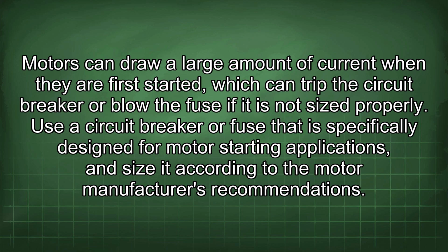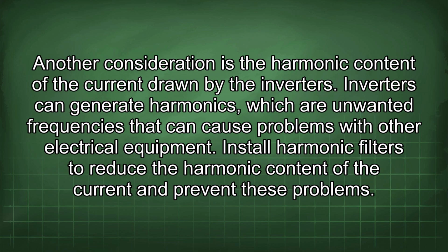Use a circuit breaker or fuse that is specifically designed for motor starting applications and size it according to the motor manufacturer's recommendations. Another consideration is the harmonic content of the current drawn by the inverters. Inverters can generate harmonics, which are unwanted frequencies that can cause problems with other electrical equipment. Install harmonic filters to reduce the harmonic content of the current and prevent these problems.